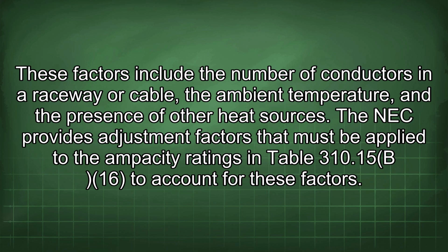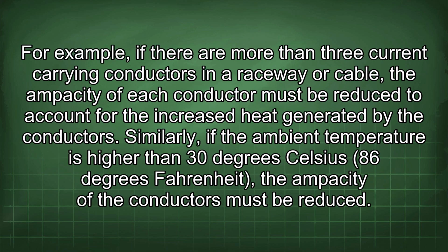The NEC provides adjustment factors that must be applied to the ampacity ratings in Table 310.15(B)(16) to account for these factors. For example, if there are more than 3 current-carrying conductors in a raceway or cable, the ampacity of each conductor must be reduced to account for the increased heat generated by the conductors.